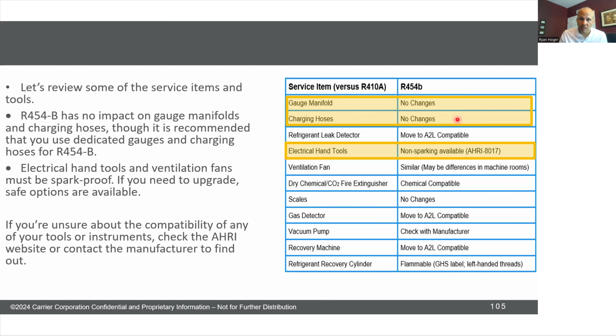What else? Vacuum pumps and recovery machines need to be A2L compatible. The ones you own might already be compatible. For most manufactured equipment, you can go to their site and get a list of the part numbers and machine numbers that are A2L compatible, or you can check the model number of the vacuum pump that you have, and it'll say on there if it's compatible or not. Essentially, is it spark proof or not? But you might not have to buy new stuff. You can just check it out that way.